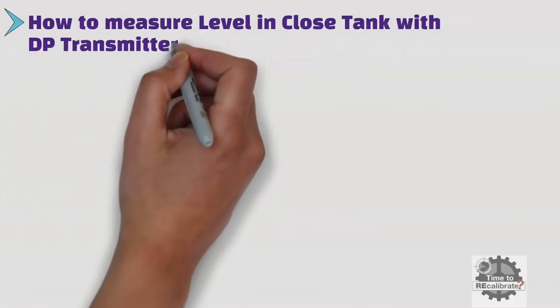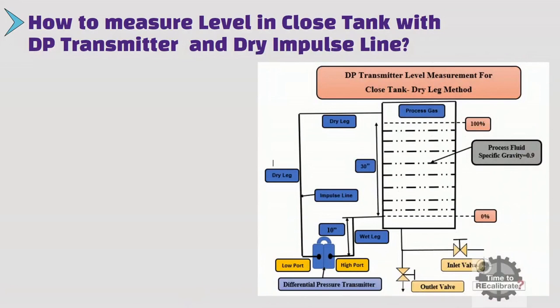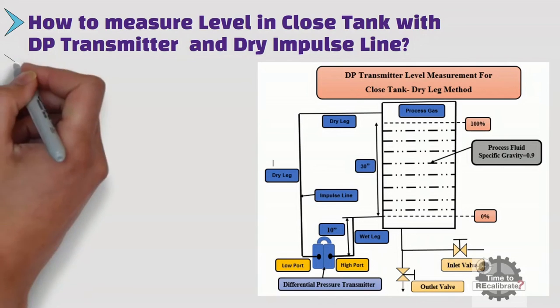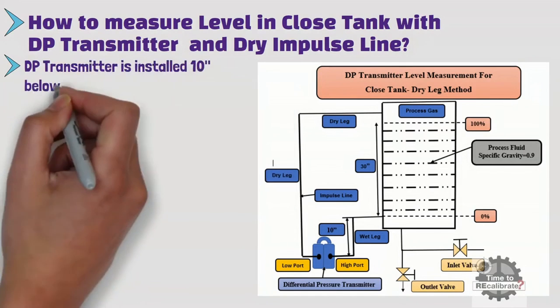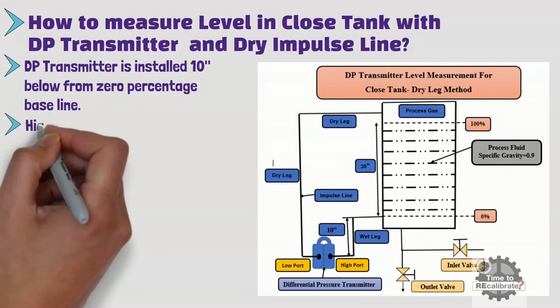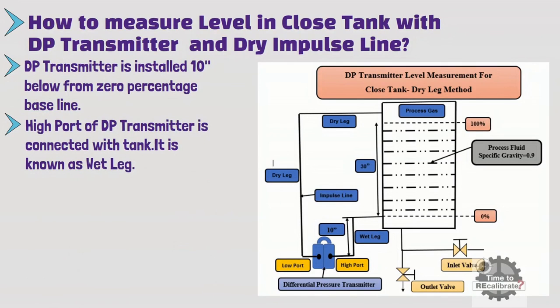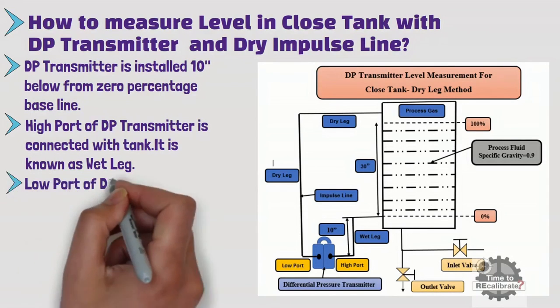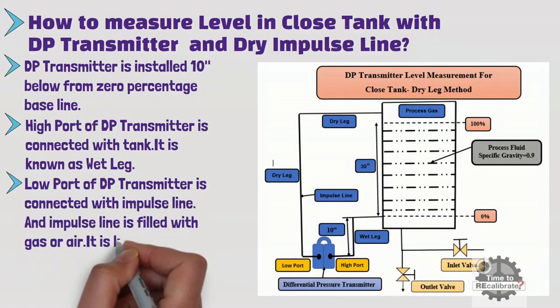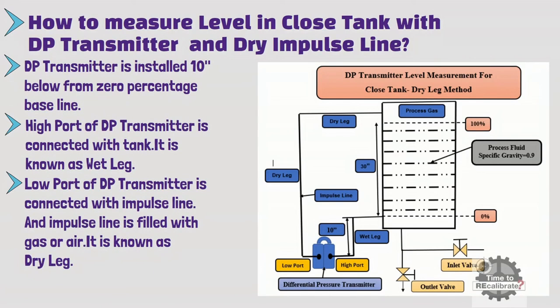How to measure level in a closed tank with a differential pressure transmitter and dry impulse line? This method is also known as the dry leg method. As you can see from the picture, the DP transmitter is installed 10 inches below the 0% baseline. The high port side is connected with the tank, and the process fluid puts pressure on the high side — this is the wet leg. The low port side is connected with an impulse line filled with gas or air, known as the dry leg. Since the impulse line is filled with gas, it does not put any pressure on the low port, so the low port has 0 inches H2O pressure.